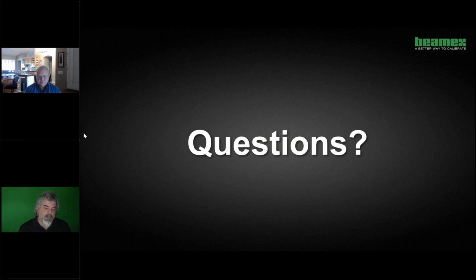Can we enter our calibration result manually? Yes, you can. There are certain instruments you can't calibrate, you do a functional check instead, and those are manual—you're functionally checking, say, a level switch. So sometimes you have to back it out to what makes sense and do a functional check, but you're still recording it.